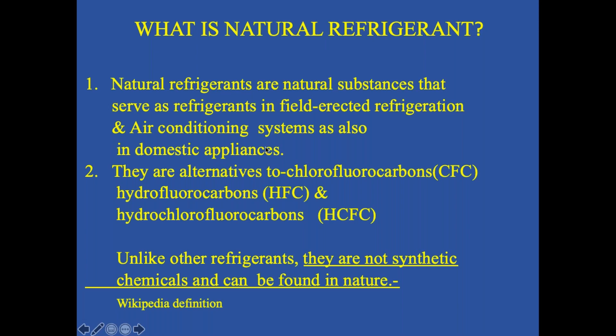Next, I have defined which are the natural refrigerants. As per the ASHRAE designation, natural refrigerants start with the digit 7, and the further two digits indicate the molecular weight of that refrigerant. For example, R717 is ammonia, in which nitrogen is 1 and hydrogen is 3. Nitrogen's molecular weight is 14, and hydrogen is 1 each, so total 17. So in 717, 17 is the molecular weight and 7 indicates it's a natural refrigerant.